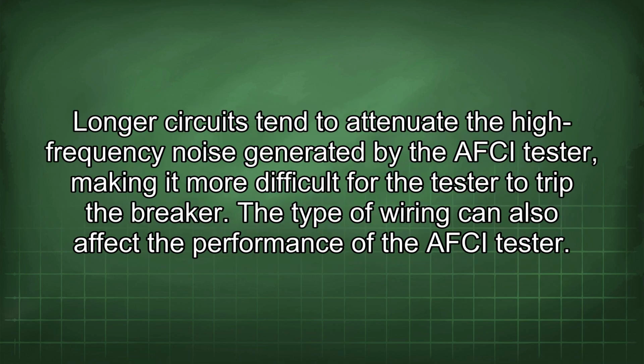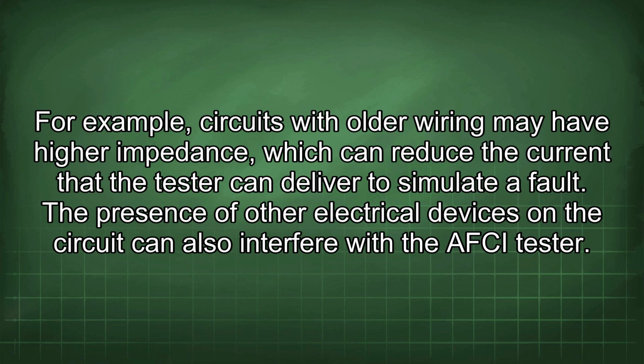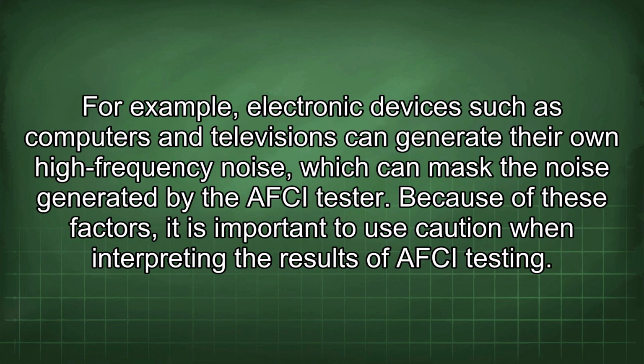Longer circuits tend to attenuate the high-frequency noise generated by the AFCI tester, making it more difficult for the tester to trip the breaker. The type of wiring can also affect the performance of the AFCI tester. For example, circuits with older wiring may have higher impedance, which can reduce the current that the tester can deliver to simulate a fault. The presence of other electrical devices on the circuit can also interfere with the AFCI tester. For example, electronic devices such as computers and televisions can generate their own high-frequency noise, which can mask the noise generated by the AFCI tester.